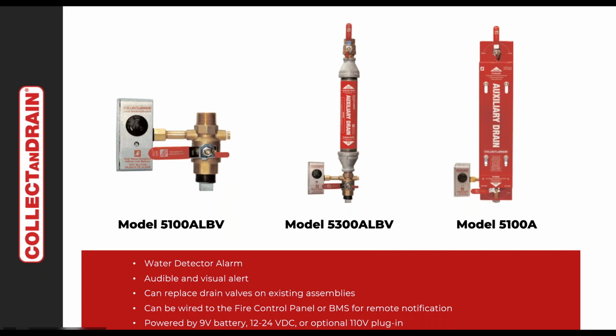So each unit comes with an onboard thermostat, and what happens is once it senses the temperature drops below approximately 40 degrees, and if that low point drain has water in it, then it will start to chirp and blink and tell you to come empty it. So this has really been a critical device component for all dry and pre-action systems to prevent problems. You can get that by itself, or you can get it as part of a larger assembly.